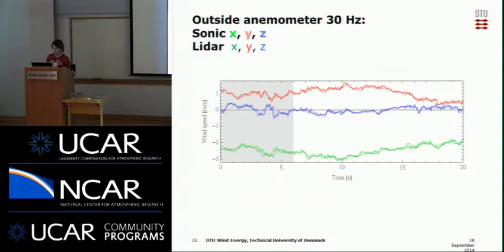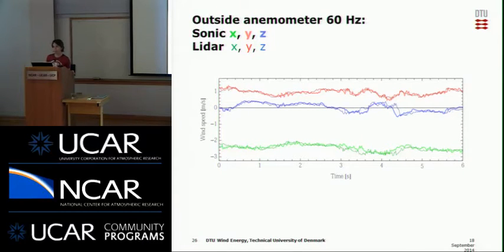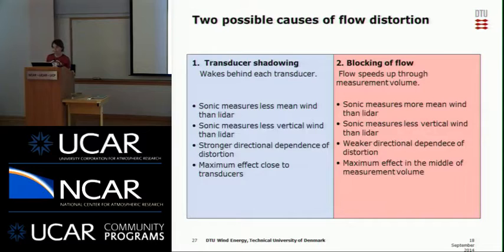Yeah, so this is 30 and then 60 Hertz. You can see quite big differences. So we now come to what causes the flow distortion, and we had discussed 2 possible causes. One is the transducer shadowing, that causes wakes behind each transducer. And the other is rather that the instrument structure blocks the flow, and then the flow decelerates on the structure and accelerates through the volume.